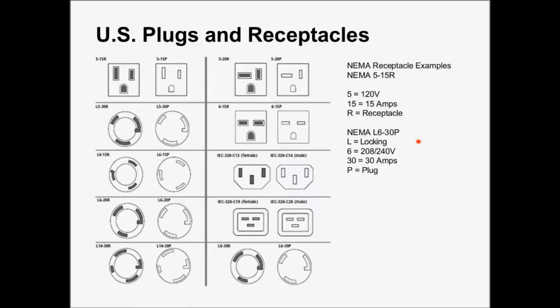If you're dealing with 208 volts, you could, for example, have the L6-30, which is this one right here, and that's L for locking. 6 is 208 or 240 volts. 30 is 30 amps, and P is for plug. And this chart is actually in the Orion catalog, so that will help you diagnose any plugs that you might run across.